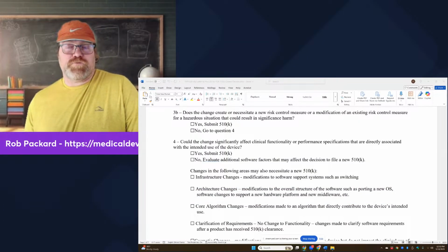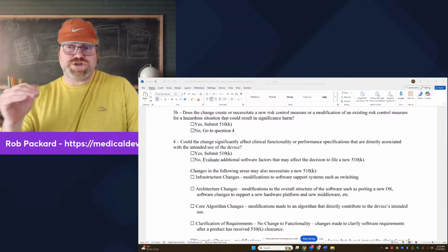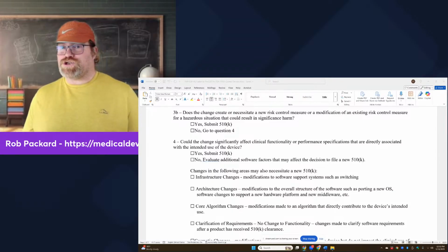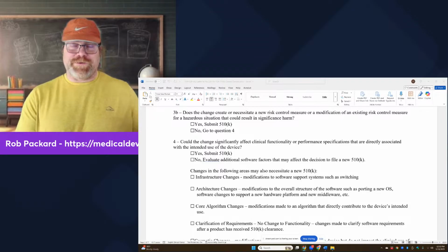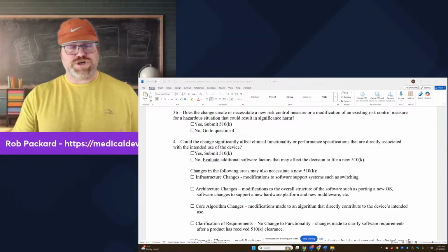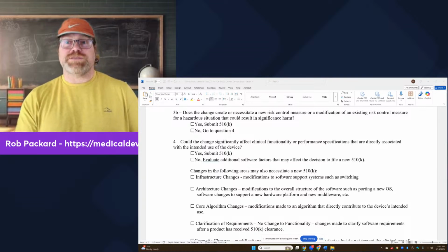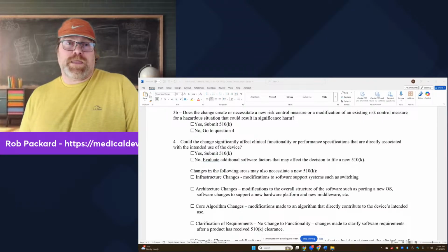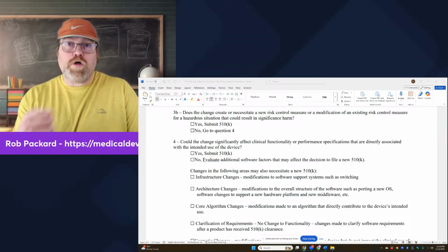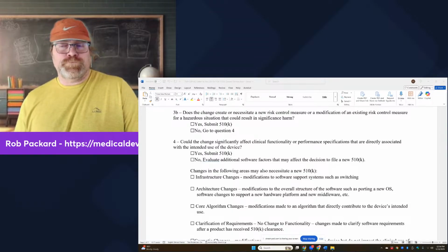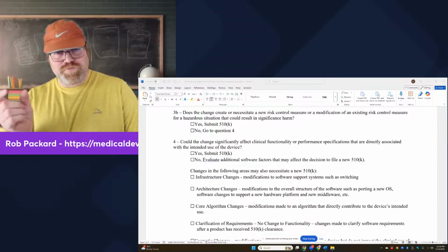But remember, when I was going through all that engineering change form, all the little things that had to be documented, you're really not doing a lot less work. It's pretty much the same amount of work, whether you're doing a letter to file or you're doing a 510K. The difference is the additional work is filling in the E-star and attaching the documents that were also attached to the engineering change note. That's the difference. And that doesn't take that much work. It's all the work doing all the validation in those test reports that really takes you the time. So think about this very carefully. It's really not a big difference.